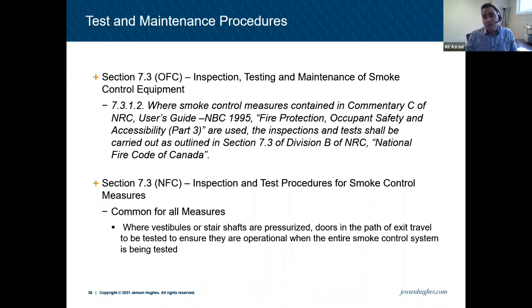Again, going back to OFC, sending you to the National Fire Code, which was asking about the inspection and test procedure for a smoke control system. If you go to 7.3 of the National Fire Code, there are certain requirements there. Some of them are common for all measures. It says where vestibules or stair shafts are pressurized, doors in the path of exit travel are to be tested to ensure they are operational when the entire smoke control system is being tested.